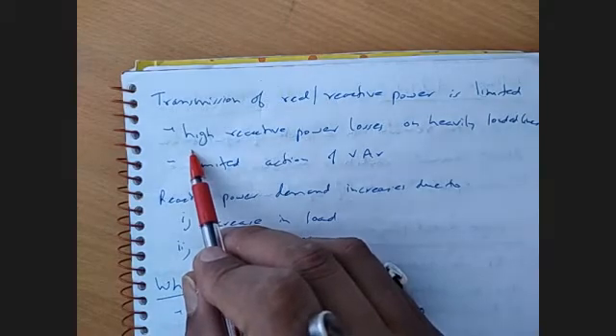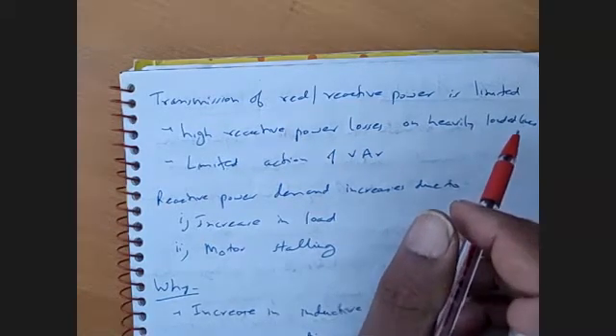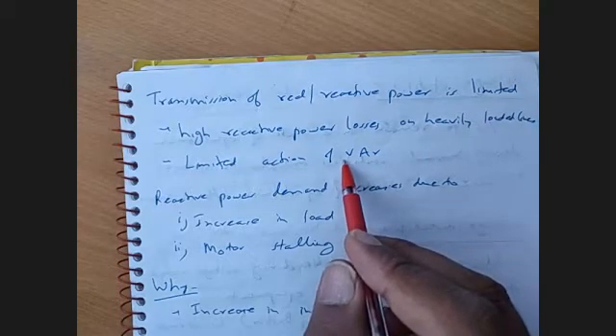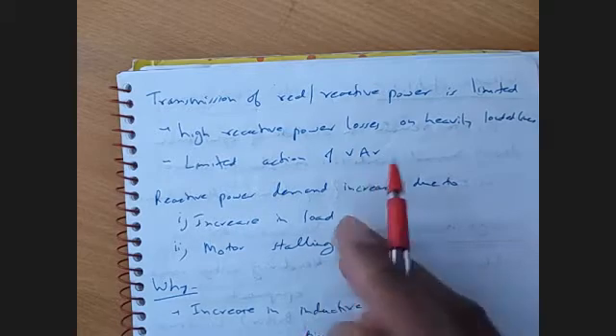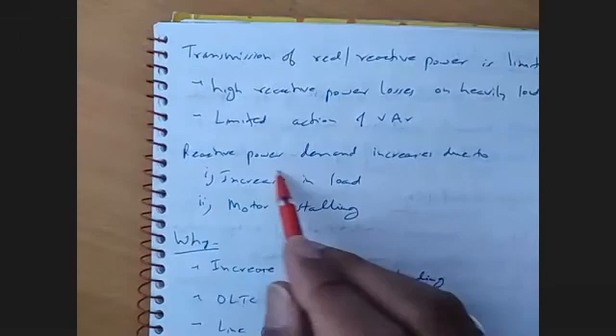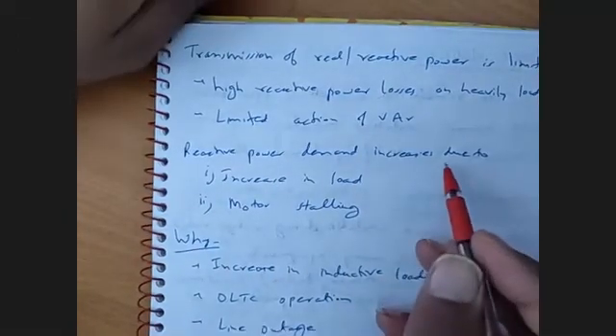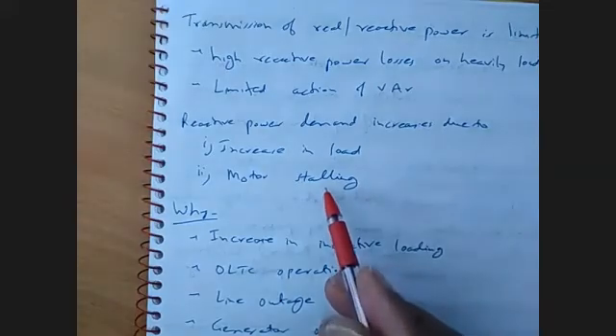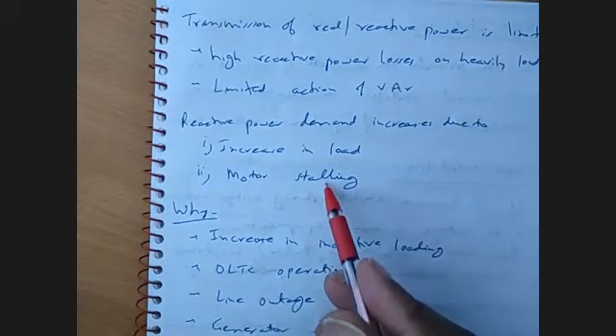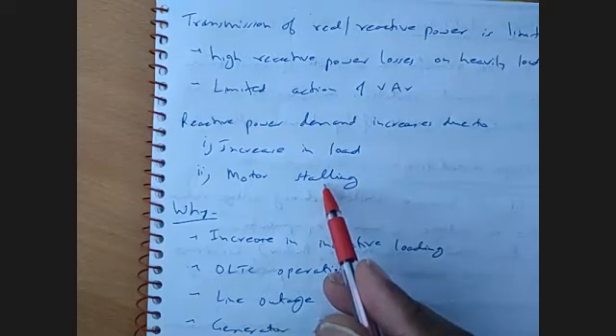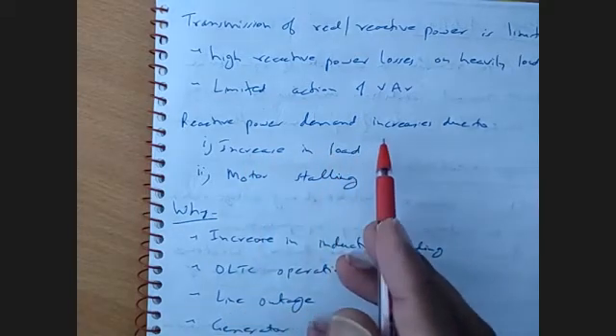of the following limitations: high reactive power losses happen in heavily loaded lines. If the lines are heavily loaded, their reactive power losses are more. And if we have limited VAR compensation, then the real power transmitted by the system is limited in the transmission lines. The reactive power demand increases due to either an increase in the load or motor stalling. That means more and more motors are coming together in the power system and motor load is increasing in the system. Then the reactive power demand of the system will increase.